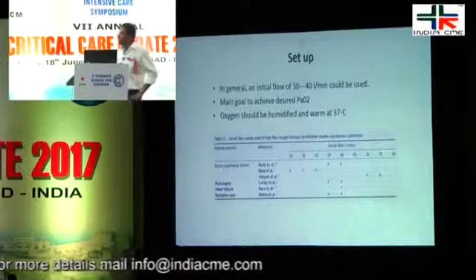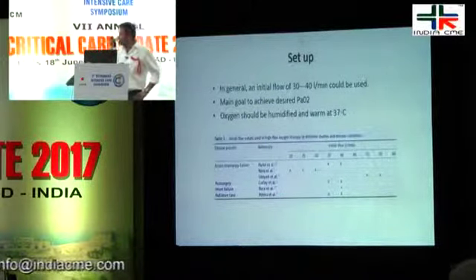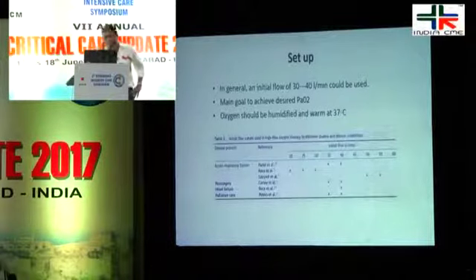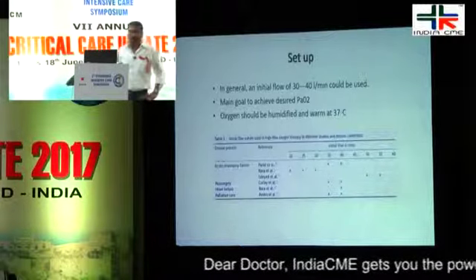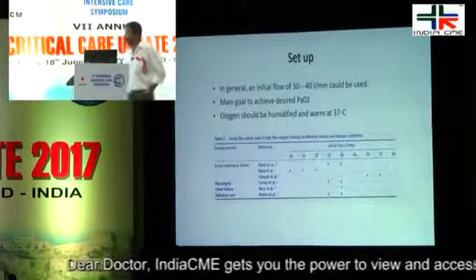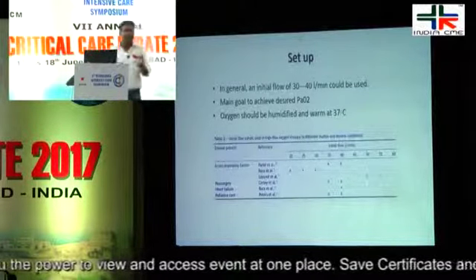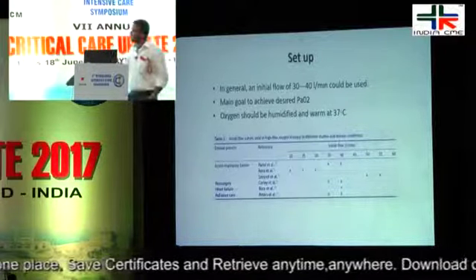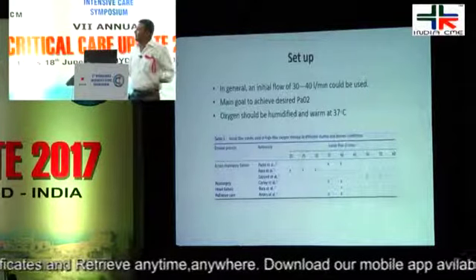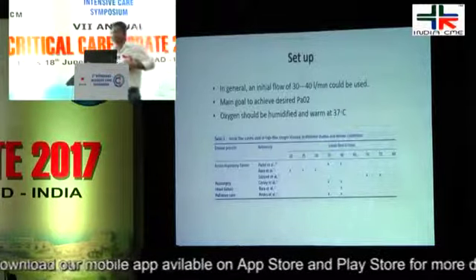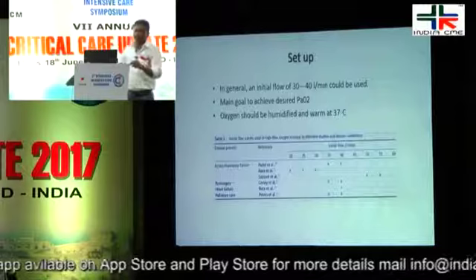Setup is pretty easy. You start with the initial flow of 30 to 40 liter per minute. We had been using it for more than a year. In fact, we were one of the first users to start it in India itself, and we found a beautiful result. I will show you some of the results. So initial flow around 40 liters. Main goal is to achieve whatever your desired PO2 or SPO2 is, right. Don't overdo it. Don't try to get 100%. Try to be happy with 95. And on the oxygen device, you have the particular settings where you have to put in the humidification and the temperature. So temperature is 37 and humidification, as I told you, close to 100%, right.